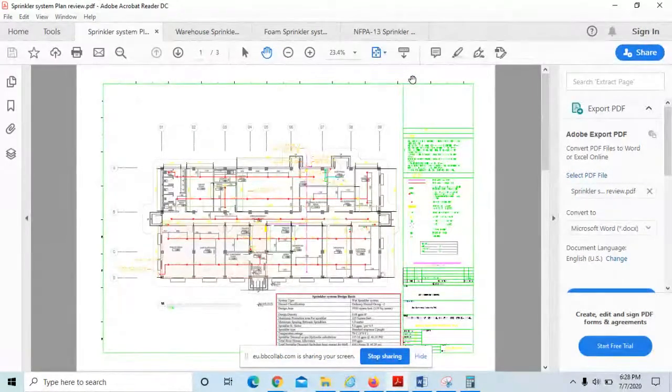Also for the branch, the maximum sprinklers in each branch must be less than or equal to 8? No, there is nothing like that. If you are following the hydraulic calculation requirement, there is no limit on that. If there are 8 sprinklers in one branch, try to start with 2.5 inch pipe, go up to some sprinklers, then give 2 inch, then 1.25 and all. So there is no limit on that. That is a limit for the pipe schedule method, not for the hydraulic calculation method.